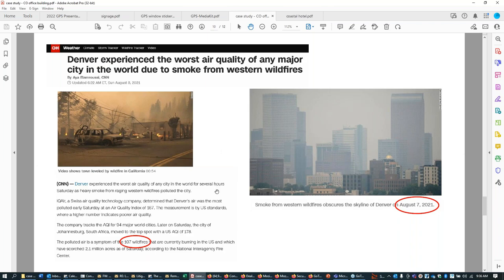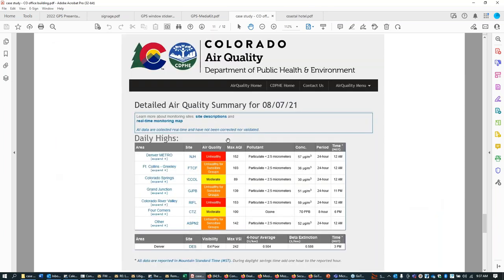That's not actually the case, because last August, you may remember, actually, sorry, 2 Augusts ago, it was August of 21, out west, there were over 100 wildfires burning in California. These were photographs from Denver, which is where my office building was, where I just showed you that case study from. And I talked to my customer about this, and the state of Colorado has a number of outside air publicly available stations. And on August 7th, they showed an air quality index range. It was very unhealthy because of PM 2.5. They had a concentration of over 55 micrograms per cubic meter.